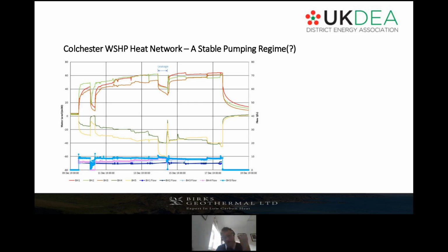And it is, but bear in mind this here is just a week, and we've got to be maintaining this hydraulic stability for 1 year, 5 years, 25 years, 50 years, and that requires good wells, and it requires a degree of investment into looking after the system through its full working life. So I've finished my presentation here. There are 2 key parameters: stable water temperature, stable pumping regime. With those 2 things, we will get the highest COP from a groundwater fed heat network.